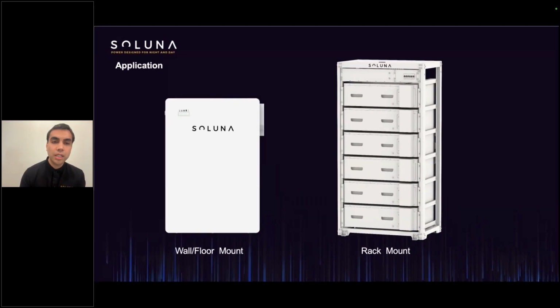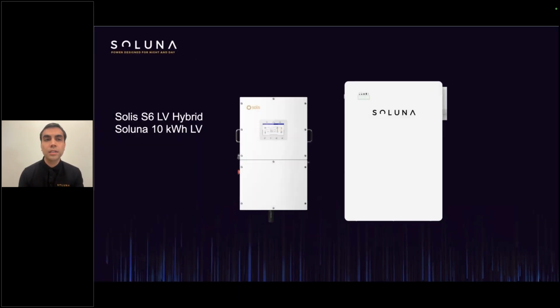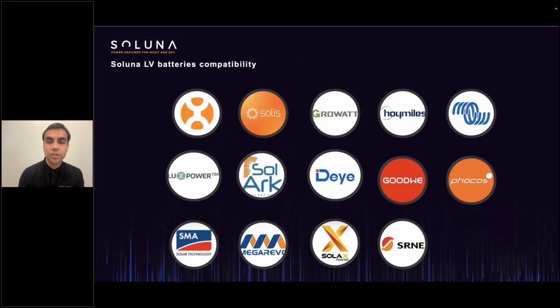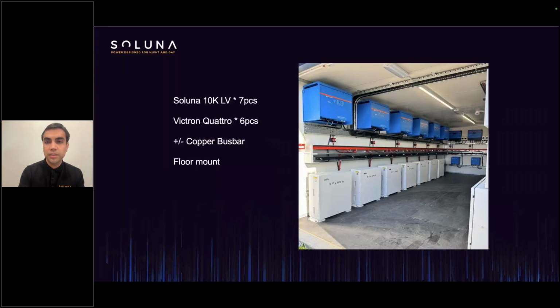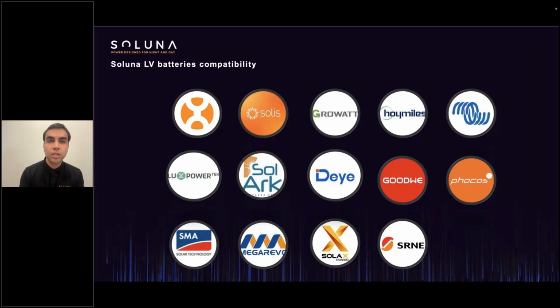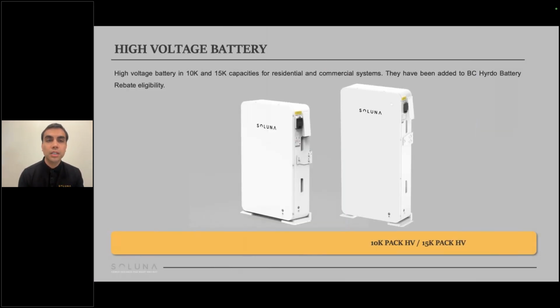For applications, you can have wall mount or floor mount, and you also have the option for a rack. It's also compatible with Solis, and it is already UL 9540 certified with Solis. This is an example with the 10K using Victron. We have multiple inverters, and if there is one inverter that is not in our list, we can always work to add it with the CAN communication. Any questions for the 10K low voltage battery?